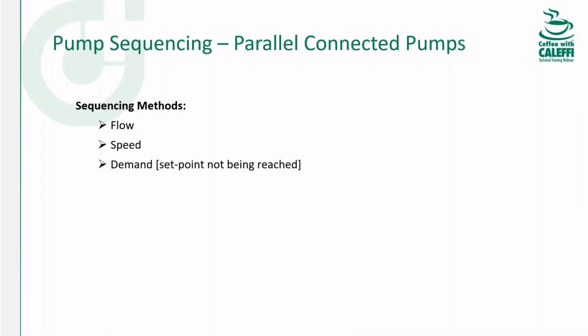Next we have demand-based sequencing. That uses PID, and it's basically, is the set point met? So if one pump's running and we drop below our 80 PSI set point, it's going to stage the next pump on. Generally this method implements timers to prevent overcycling. But that means if a pump turns on, it's going to stay on for whatever that time is, 5 minutes or 10 minutes, even though the demand is not there. So you've got a pump running when you don't need it. It uses some PID control, and it's a step in the right direction, but it's not the best.